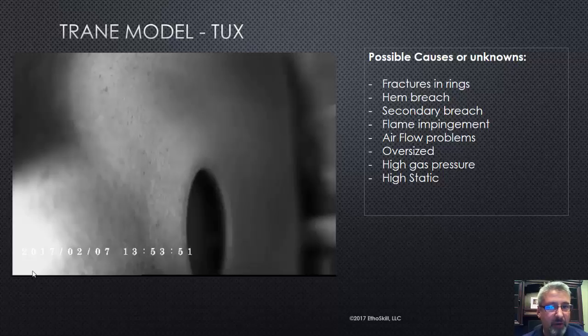So let's talk about the unknowns. Number one, are there fractures in the rings? I believe there were. Could we have a breach in that hem? Heat exchanger, hem, that crimped hem, if that opens up, gets a little loose and sloppy, you have to remember, some of these furnaces cycle thousands and thousands of times per winter. One heating season where I live is 5,000 to 7,000 times. Well, that's a lot of expansion and contraction. That hem can open up, and you may not see it.